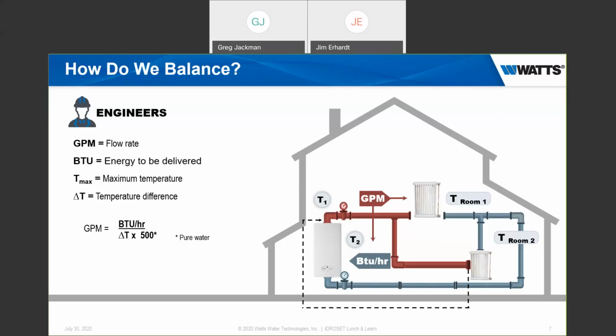Conversely, if we flow too much, if we just over pump that heat emitter, what'll happen is the delta T will get smaller. In other words, instead of a 20-degree delta T, we may have a 10-degree delta T or even a 5-degree delta T. And as that delta T shrinks, both chillers and ModCon boilers, modulating condensing boilers, become less efficient. Specifically, modulating condensing boilers really depend on the coolest water possible coming back in the return to keep them in condensing mode. So once we start over pumping, one of the big problems is going to be loss of efficiency. We also have the potential of having velocity noises in the piping system by over pumping.